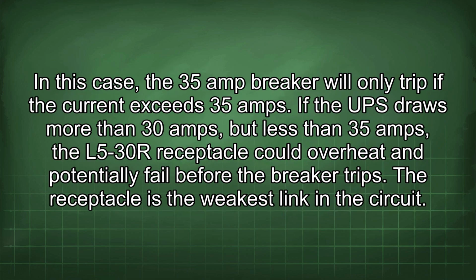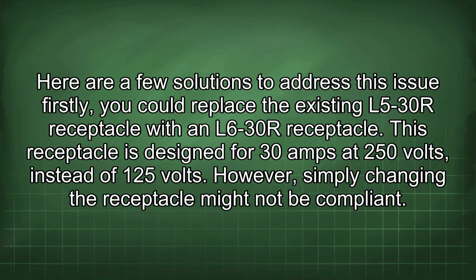In this case, the 35 amp breaker will only trip if the current exceeds 35 amps. If the UPS draws more than 30 amps, but less than 35 amps, the L5-30R receptacle could overheat and potentially fail before the breaker trips. The receptacle is the weakest link in the circuit. Here are a few solutions to address this issue.